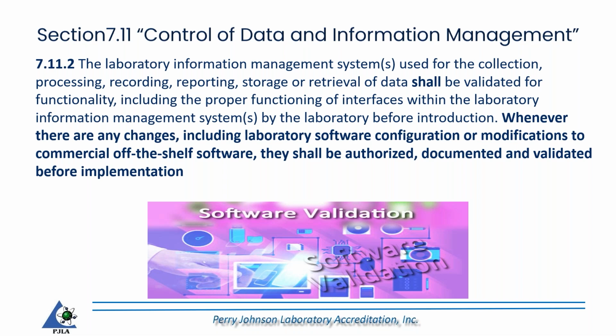7.11.2, the laboratory information management system used for the collection, processing, reporting, storage, and retrieval of data shall be validated for functionality, including the proper functioning of interfaces within the laboratory information management system, by the laboratory before introduction. Whenever there are changes, including laboratory software configuration or modification to commercial off-the-shelf software, they shall be authorized, documented, and validated before being implemented.